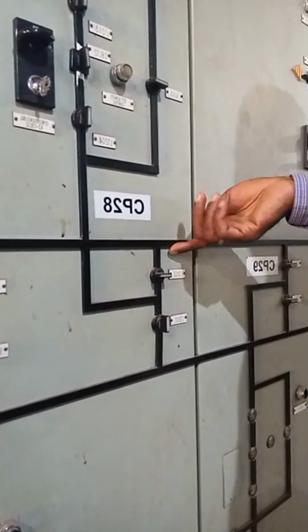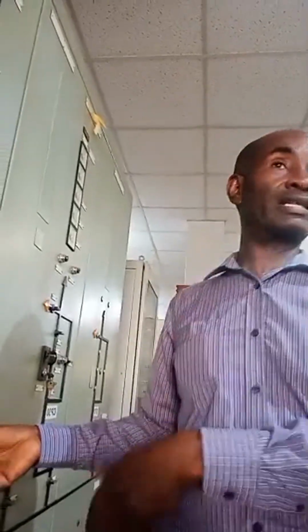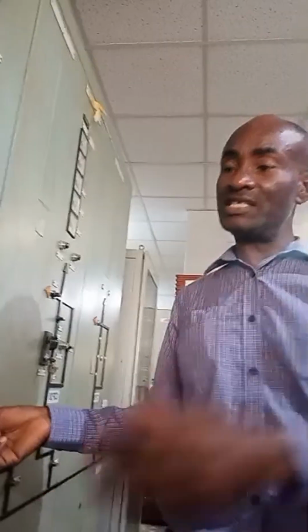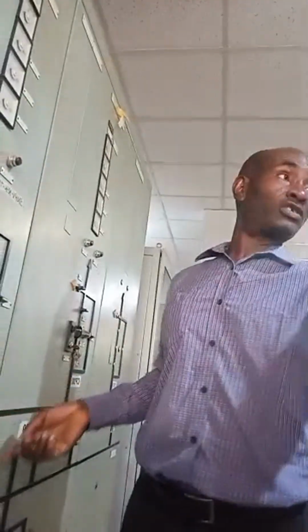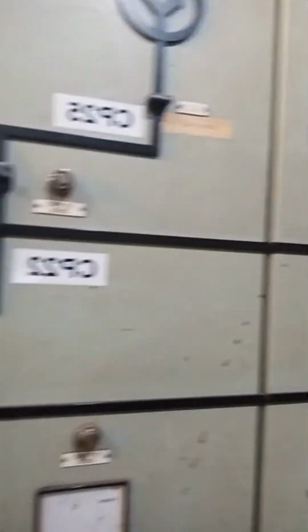So now, what differentiates this one from the other, like all other equipment connected to it, is that this one has what is called a bus coupler CB, a bus bar coupler CB that couples - not section, don't bring in section, right - it couples this bus bar and that bus bar and maintains the two bus bars at the same potential, is that okay?